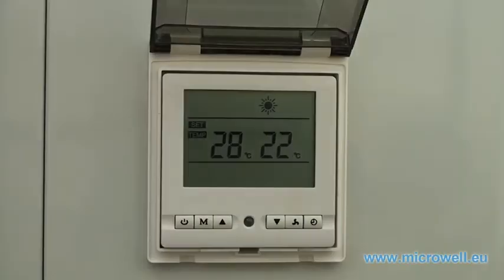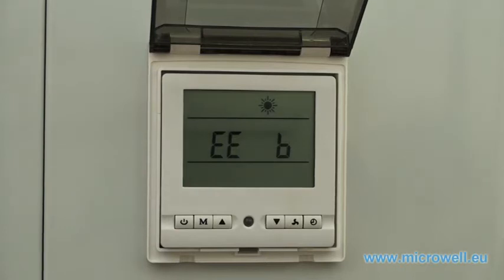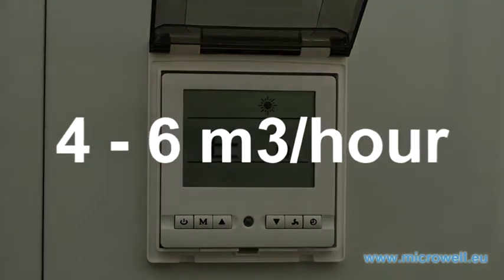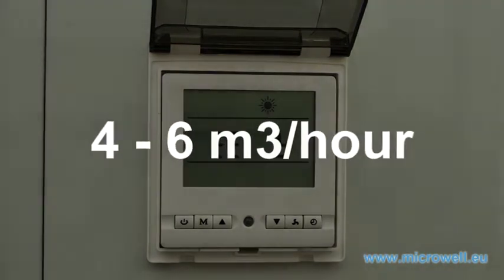There is no reason for the heat pump to operate under these conditions and it is perfectly normal for it to switch itself off. Proper water flow needs to be ensured in levels from 4 to 6 cubic meters per hour.